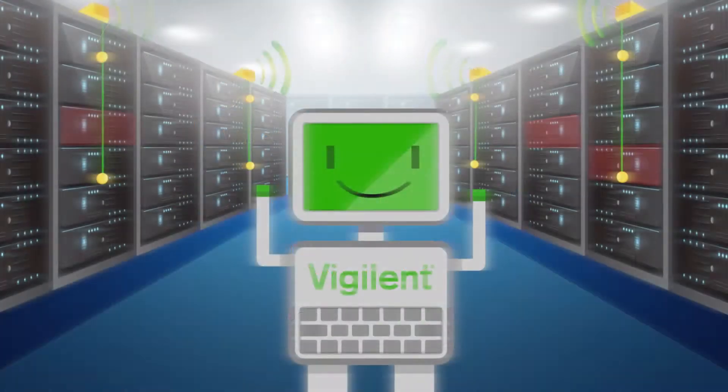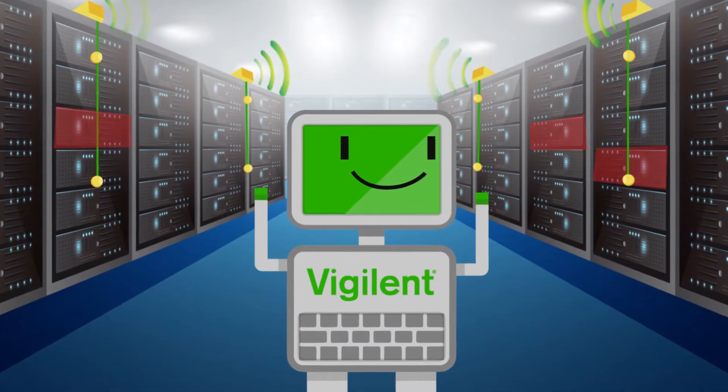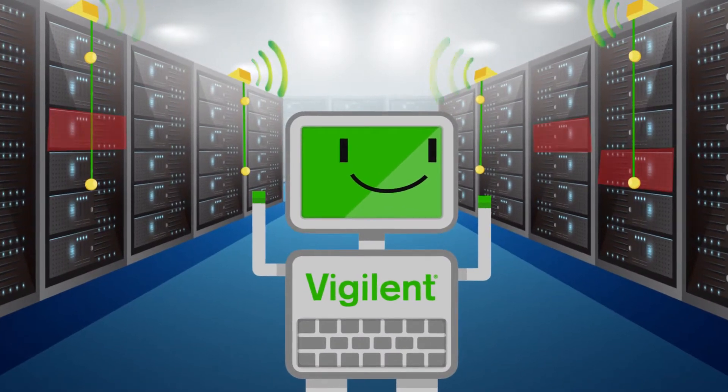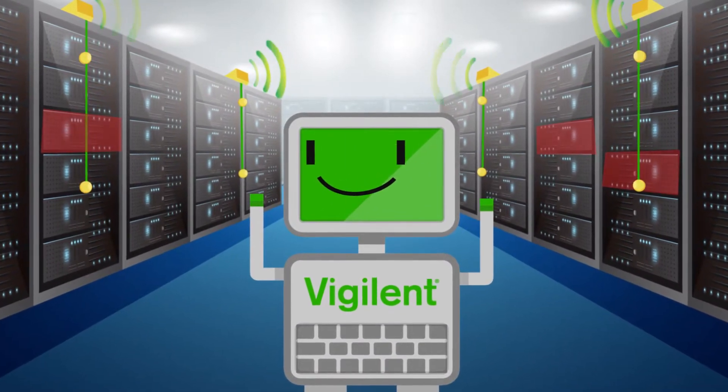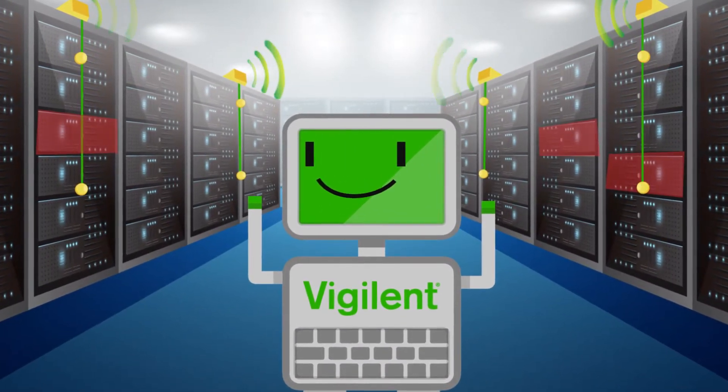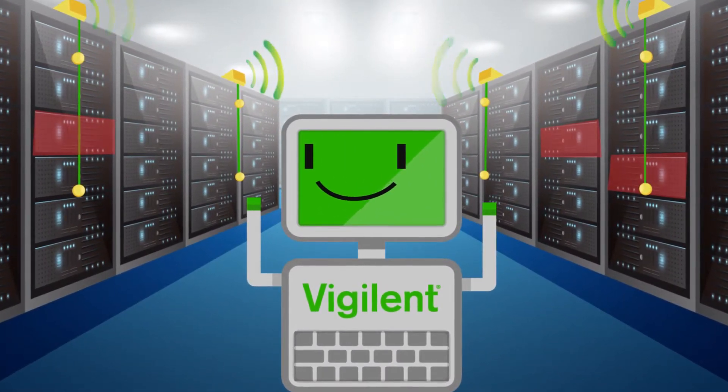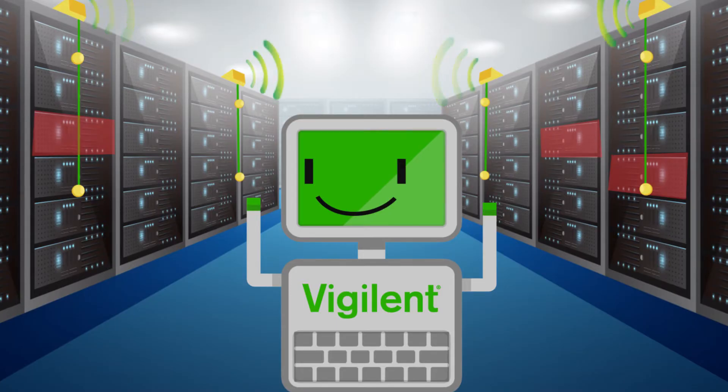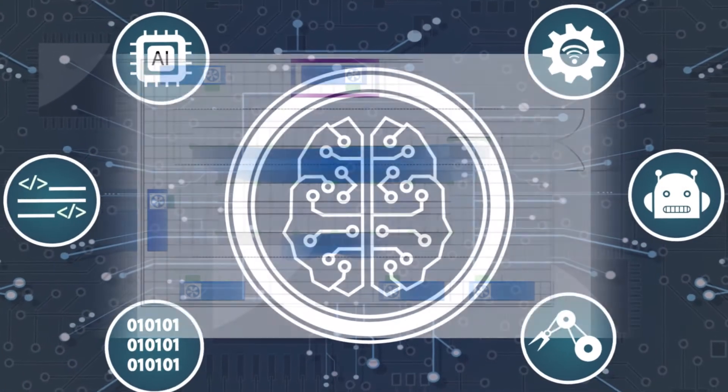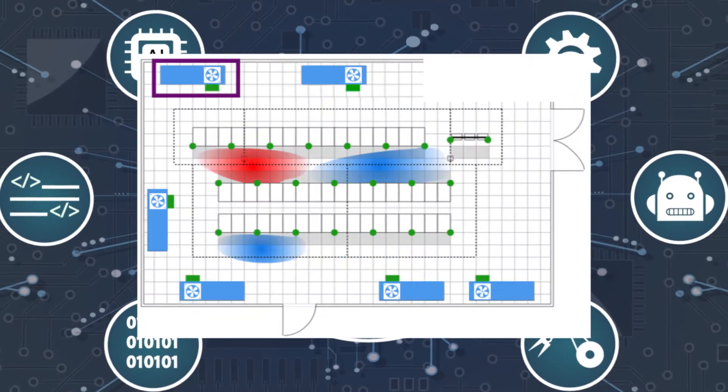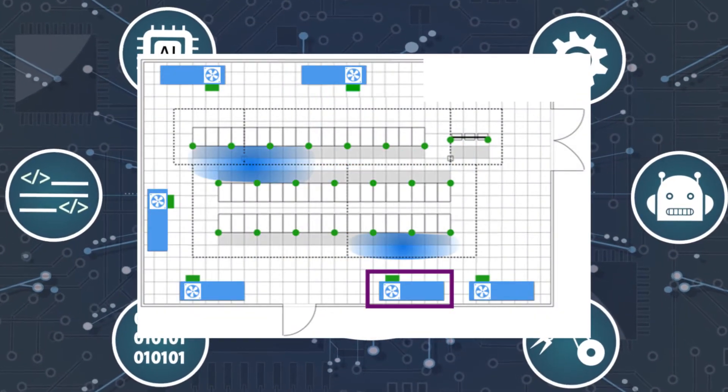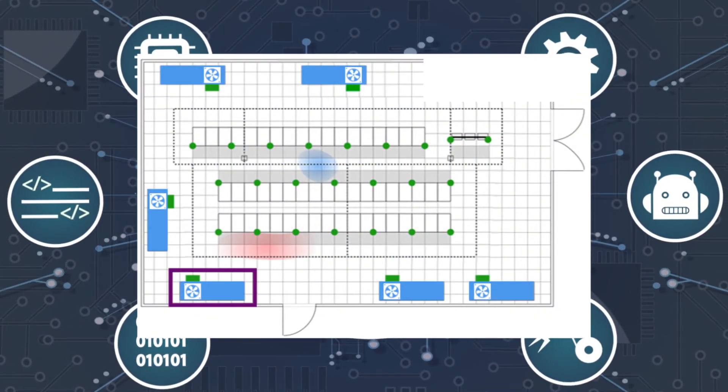Here's how it works. Artificial intelligence software takes temperature readings from sensors throughout the data center and uses machine learning to discover the thermal influence of each cooling unit on the environment.